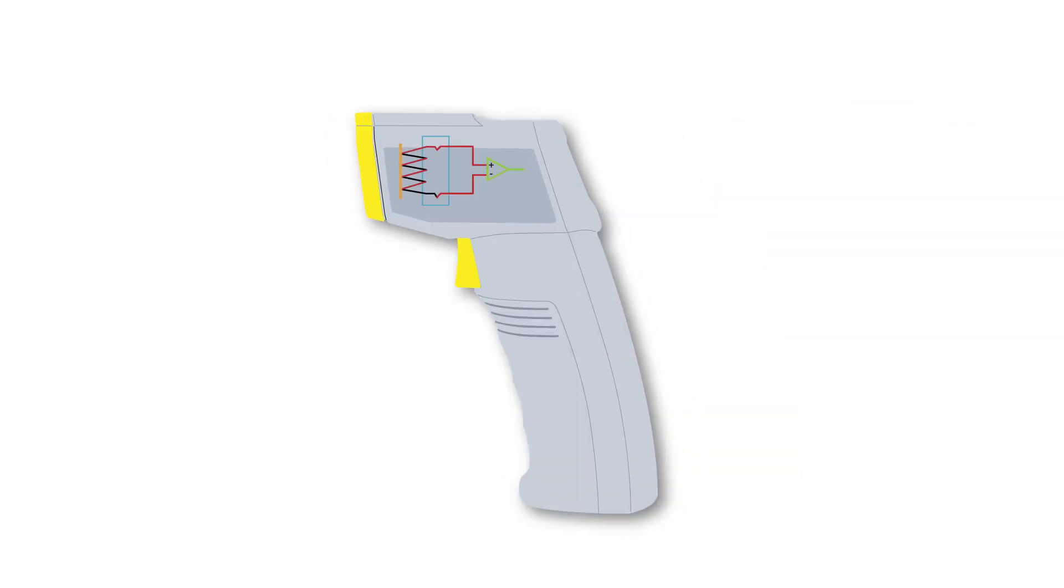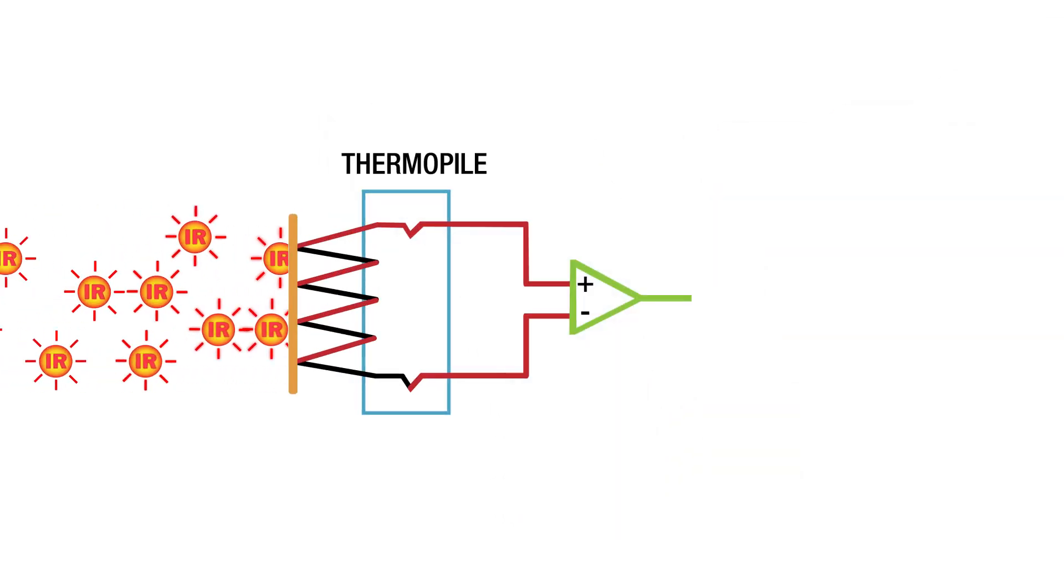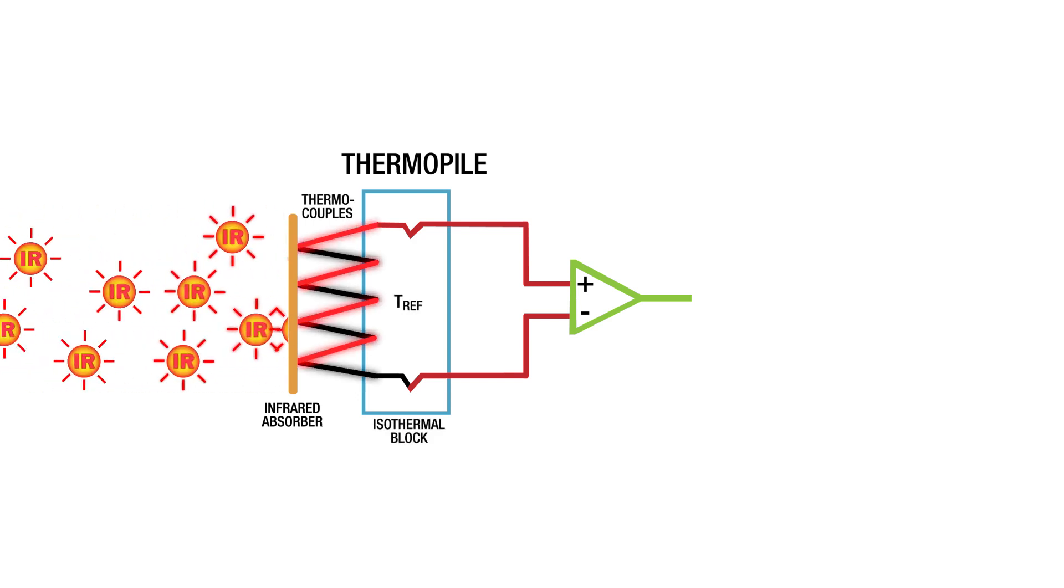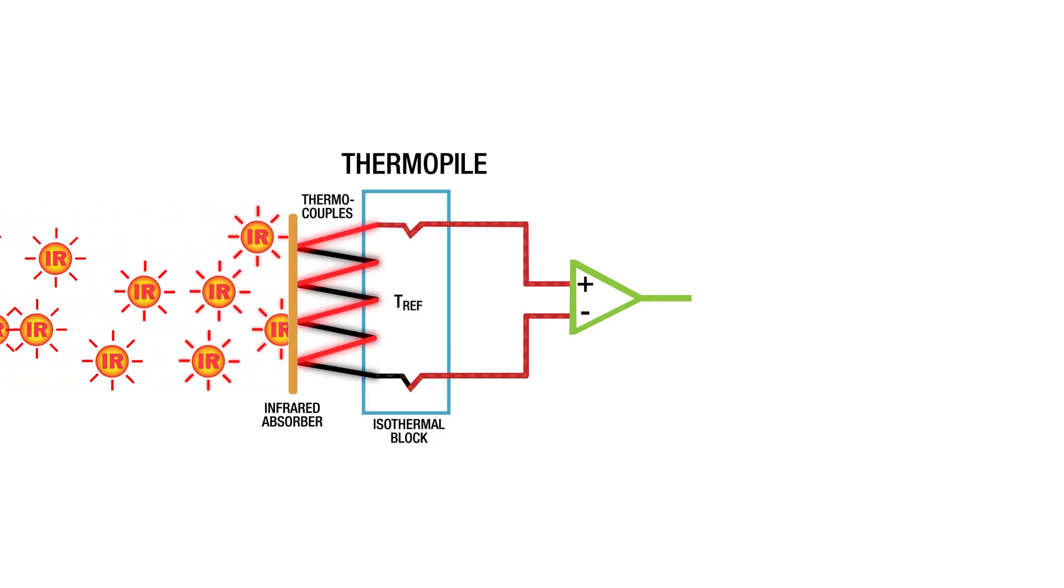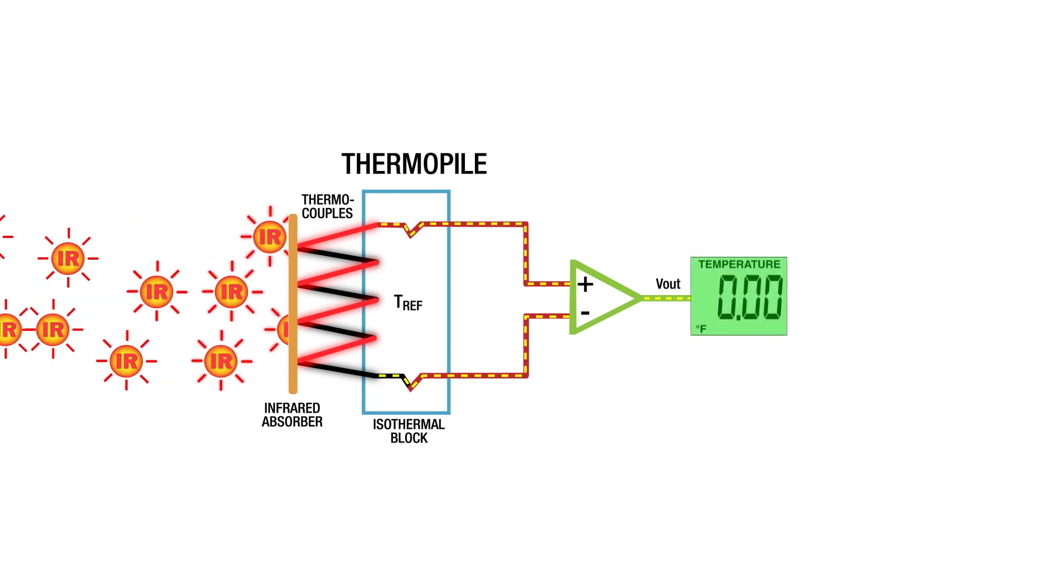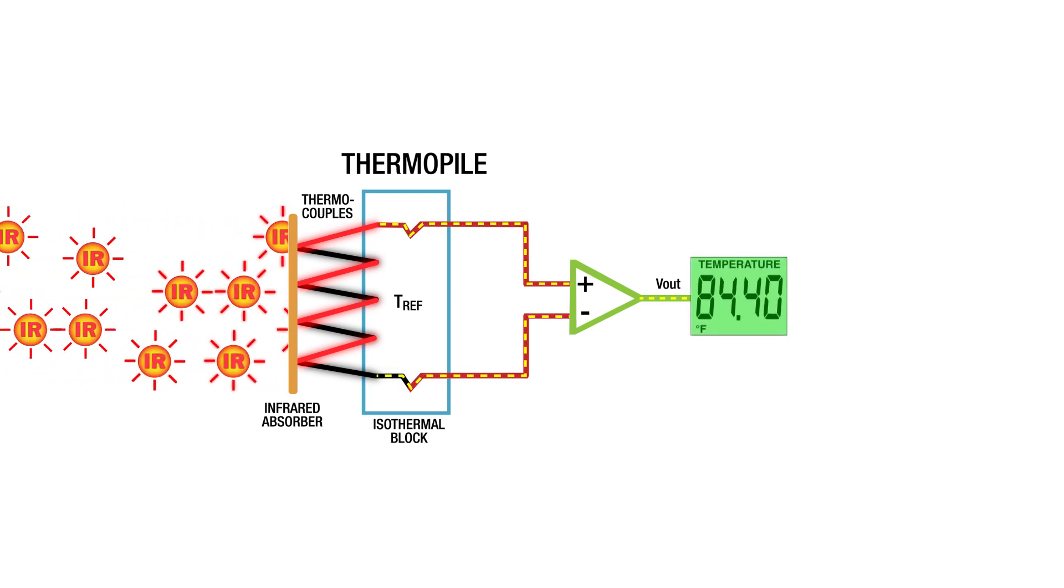An infrared thermometer uses a sensor called a thermopile, which turns the incoming infrared radiation into heat using tiny thermocouples. The thermocouples convert that heat into an electrical signal, which is measured and displayed on the screen in the form of a temperature reading.